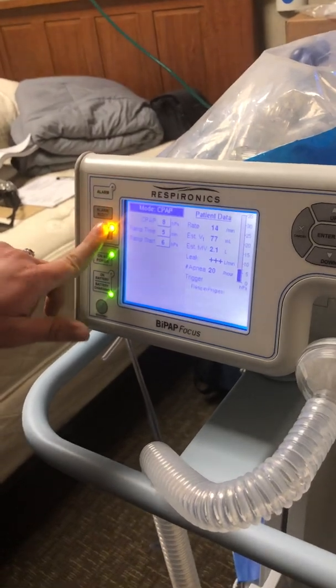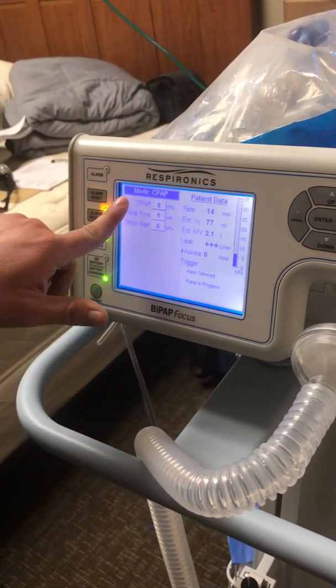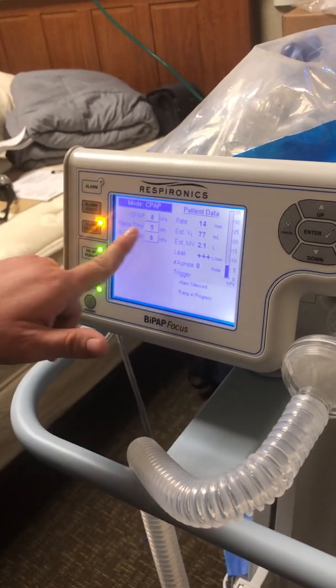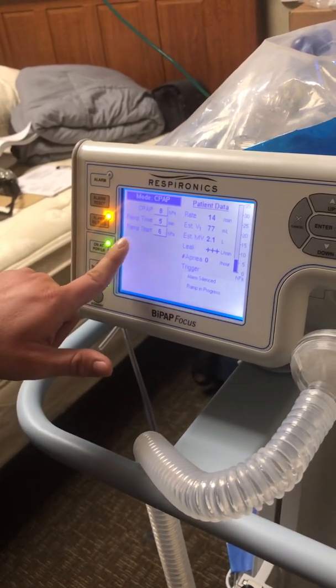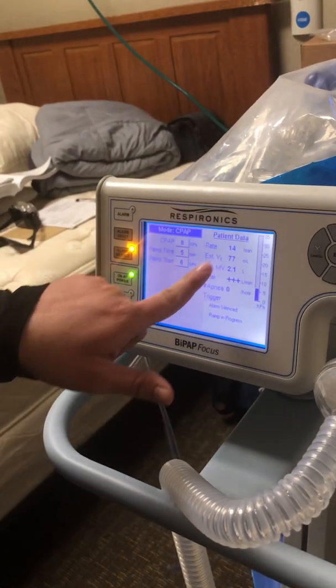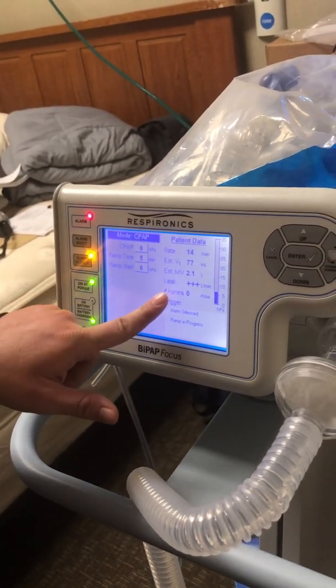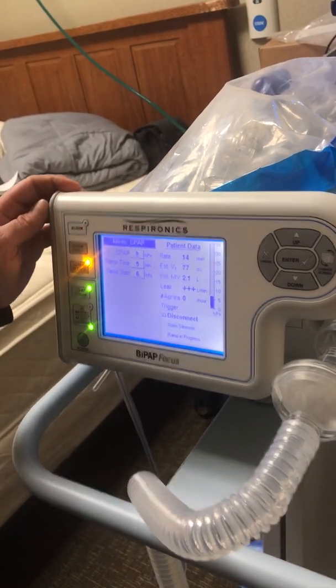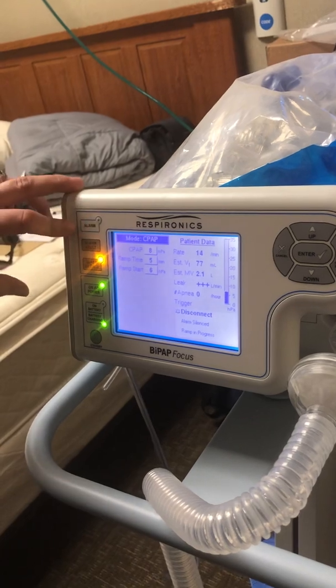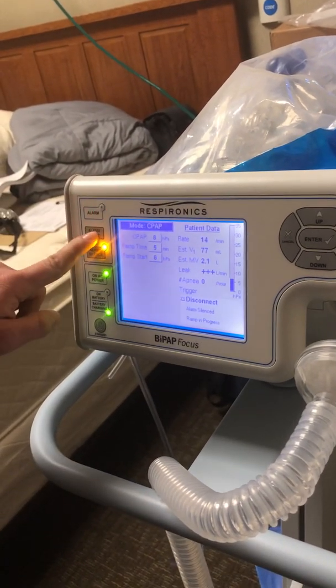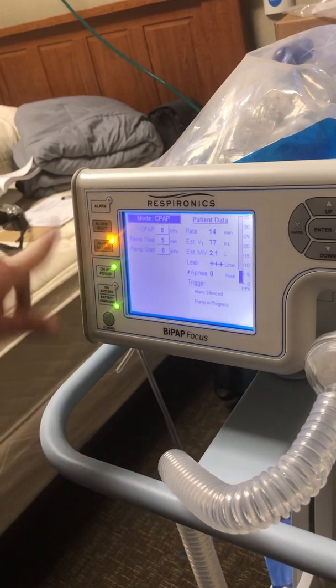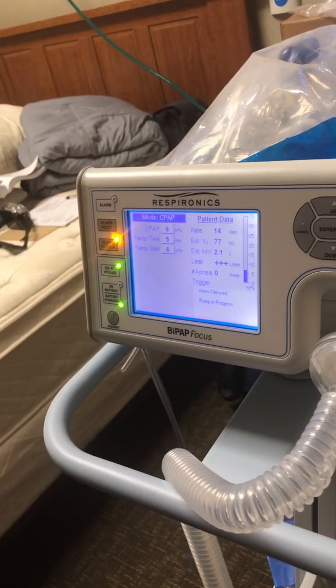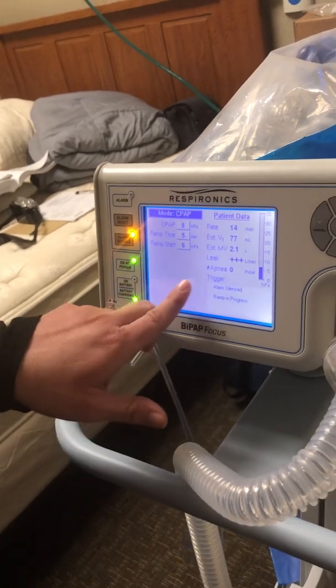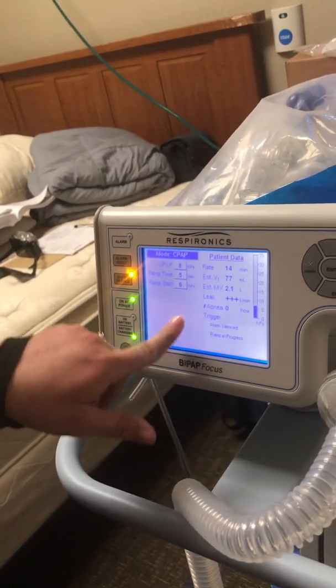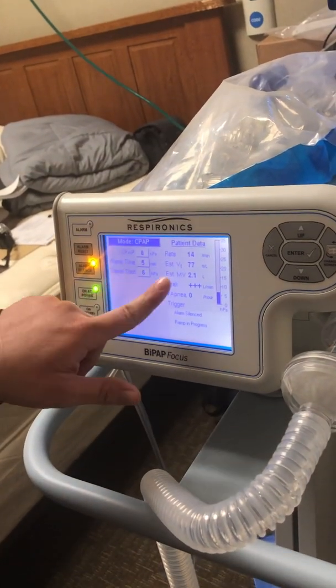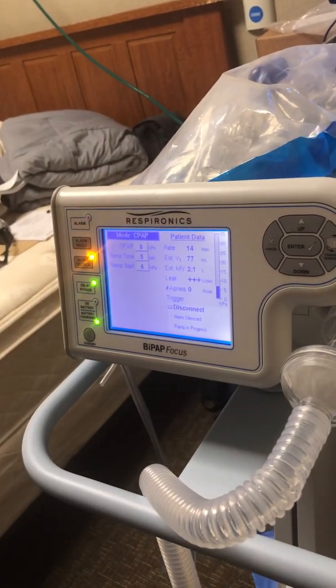And then here you'll see it has your main screen. It'll show you what you have your set CPAP at, their ramp time, every 5 minutes, and their ramp start. And then over here again is all the patient's data that it goes by. So when your alarm goes off, you'll have a flashing light over here that the alarm is going to sound. So what you're going to do is hit alarm reset and alarm silence, so that way you can silence the alarm and check to see what is going on, see why the alarm went off, if there's a leak in the patient, if their rate and everything is not quite right together, anything like that.